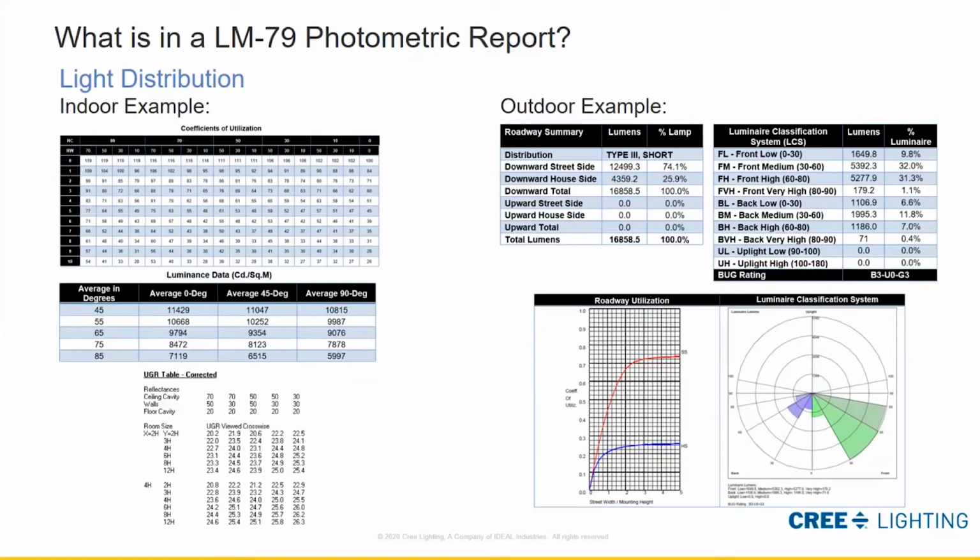And it's something that's come out of Europe and has only started to be adopted in the United States, particularly by the DLC, to try and understand better performing glare products, and how glary something might or might not be in an application. So a value of, say, 23 or 22 might be good for a troffer. It might be different for a high bay. So it's all application specific, and you can apply it to your room that you are generating or looking at to design for.